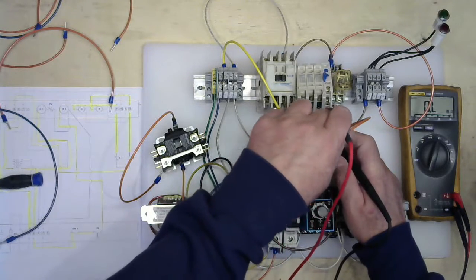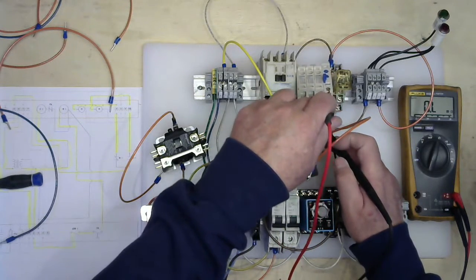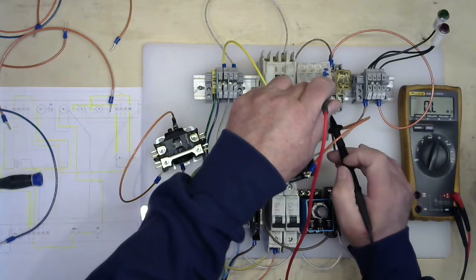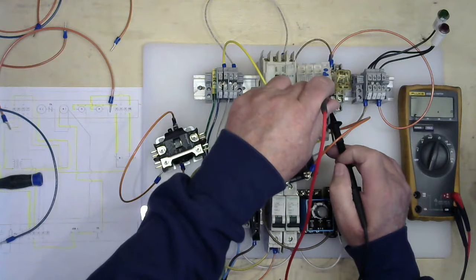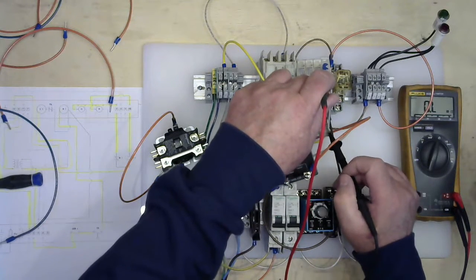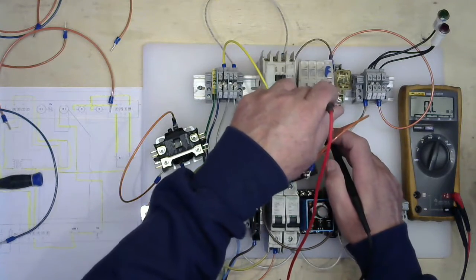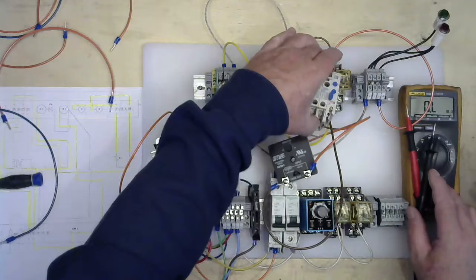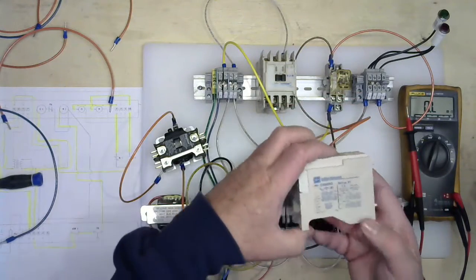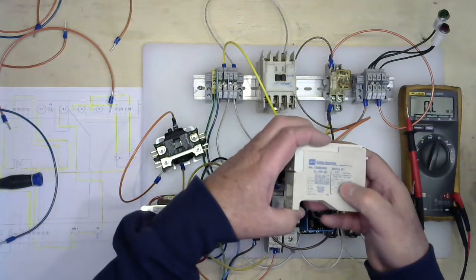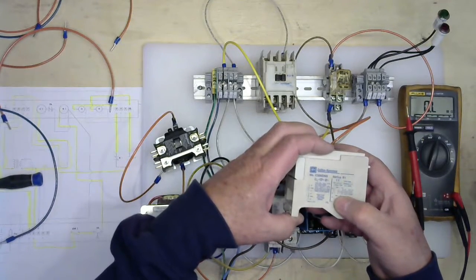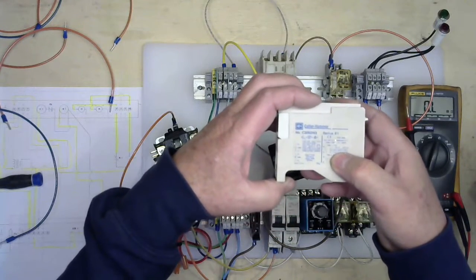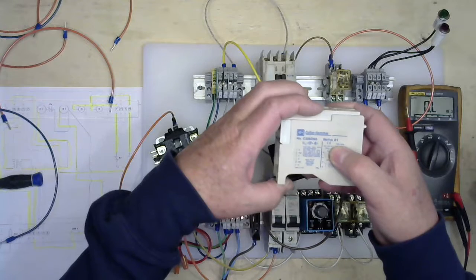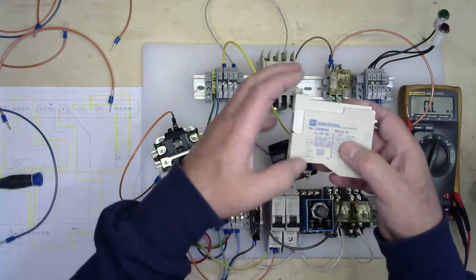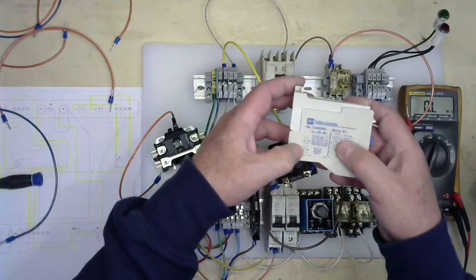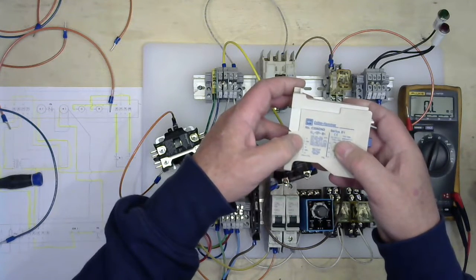Is it this one is normally closed? No. Or is this one normally closed? I have continuity through the meter. Overload is here. I do not have continuity through there. Before I put my wiring connections together, you can look on the side of your overloads. That will tell you the contacts. It tells me 95 and 96 here are normally closed, and 97 and 98 are normally open. And then it kind of gives you a set of contacts on the bottom. 95, 96 are closed, 97, 98 are open.